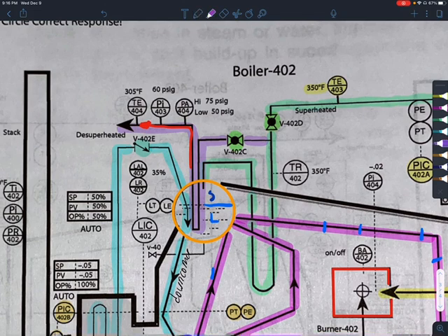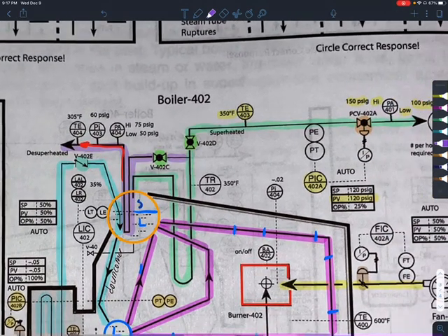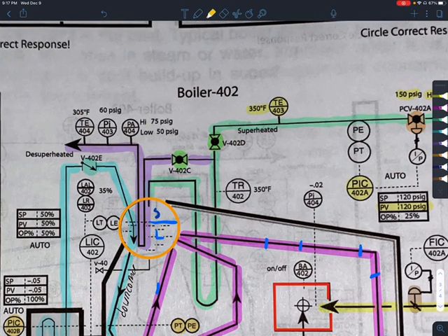and now it visits a pressure alarm system, a pressure indicator, and a temperature element, okay? This is now reading 60 psig. So from 120 psig all the way to 60, cuts it in half, okay? And these pressure alarm systems, what was that, yellow? Isn't that yellow? I was like this color. There we go. It will go off if it reads 75 psig, and the alarm will go off if it reads 50 psig, okay? When it's high, when it's low, okay?